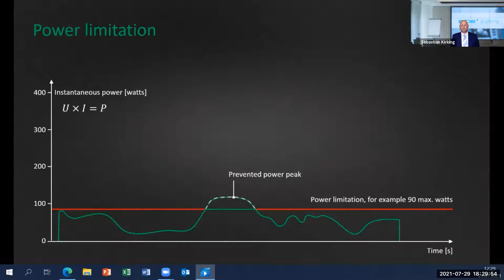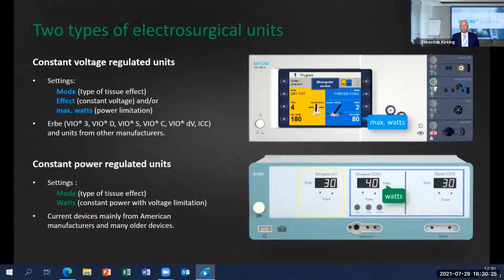Make sure to know which type of electrosurgical unit you're using, because other units might have a power control where you cannot set the peak voltage, but the resulting electric power. The settings are definitely not the same and cannot directly be compared. You can identify these units by the unit of their settings. If they say watts, it is a power control unit. If they say effect with the unit volts and max watts for the power limitation, it is a voltage controlled unit.